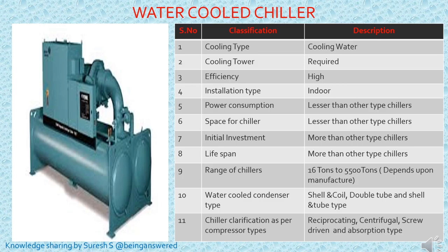Now we will see the water cooled chiller. The name water cooled chiller means the mechanism of cooling the condenser through water. That's why it's called a water cooled chiller. For this we need a dedicated cooling tower to cool the condenser, so it will be a separate unit. The efficiency of the chiller will always be high because the cooling tower is involved in this cooling process.